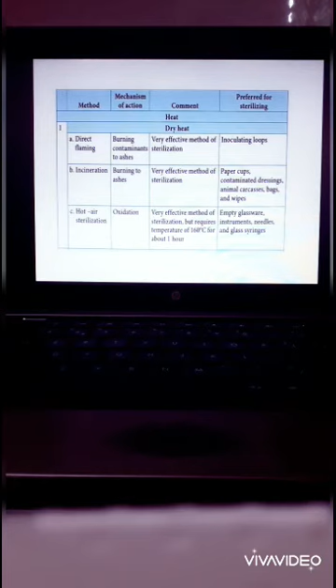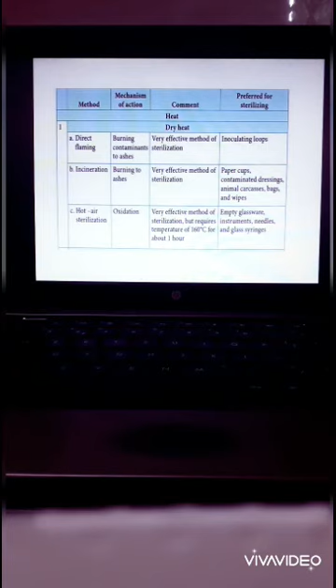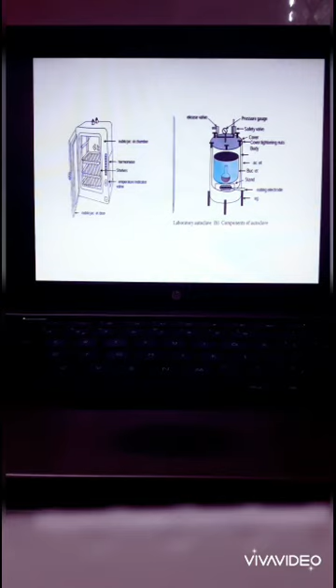hot air sterilization. The mechanism is oxidation. It is a very effective method of sterilization but requires a temperature of 160 degrees Celsius for about 1 hour, and in this process the proteins are coagulated. We prefer this method for empty glassware, instruments, needles and glass syringes. This is a laboratory autoclave and hot air oven which we use for sterilization. The hot air oven is used for dry heat sterilization, whereas the autoclave is used for wet heat sterilization.